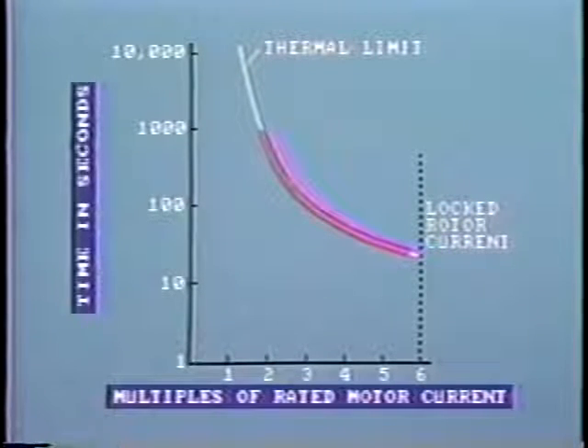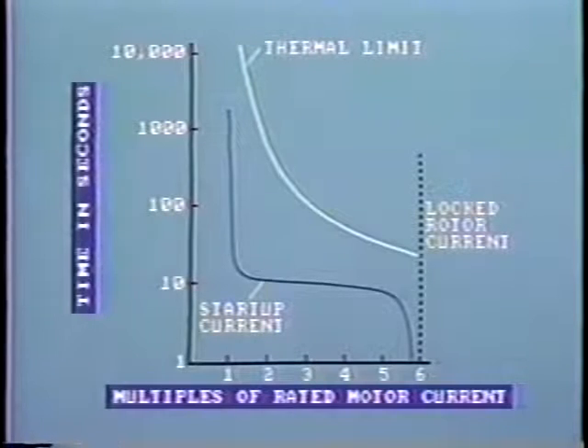The center portion of the curve shows the current limits that are recommended while the motor is running up to speed. We can also show on this same diagram the curve that represents the stator current during startup. As you will remember, starting current is about 9 times normal rated, but within a few milliseconds, this falls to just under 6 times. This is approximately the same value as the locked rotor value, as you would expect. After about 12 seconds, the current falls to normal rated value as the motor achieves normal operating speed.